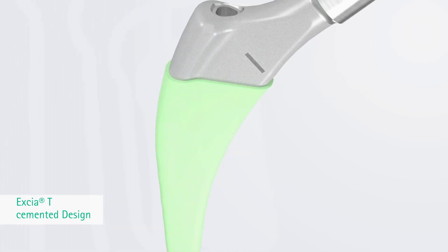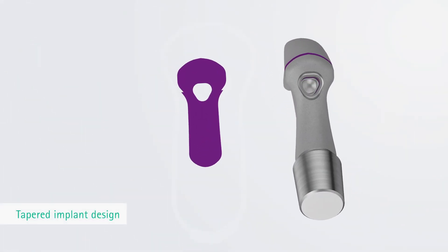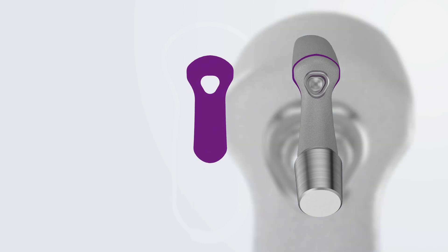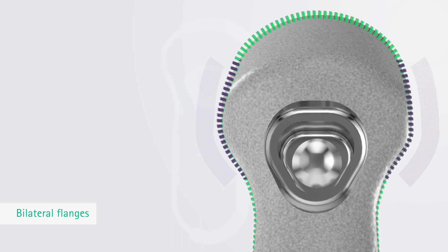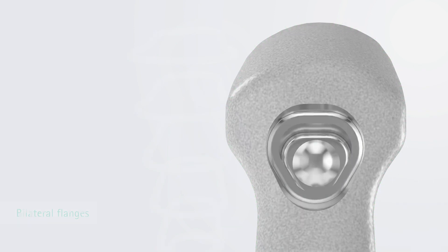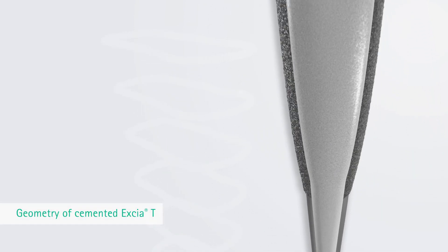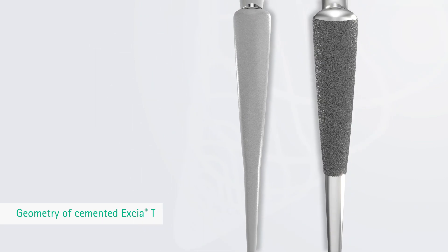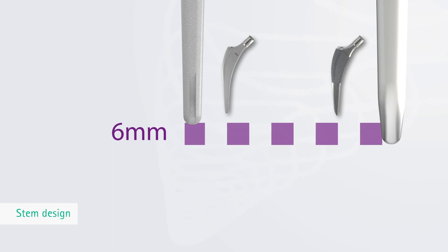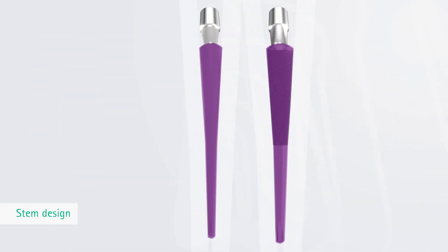Excia T Cemented Design. The tapered implant design with the trochanter-preserving shoulder geometry has also been adopted for the cemented Excia T stem. The bilateral flanges in the trochanter area support the proximal fit of the implant in the cement mantle. The geometry of the cemented Excia T is parametric to the cementless Excia T stem. The stem design is 6 mm shorter for all sizes and has been radially reduced by 1 mm along the complete stem.